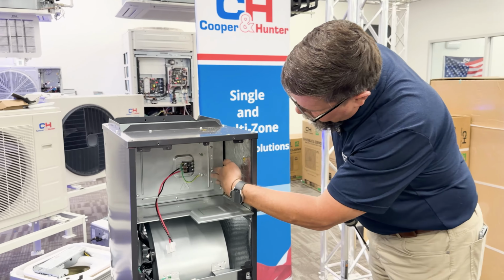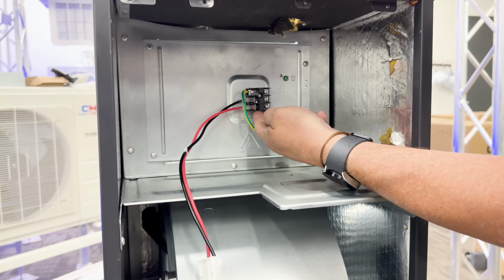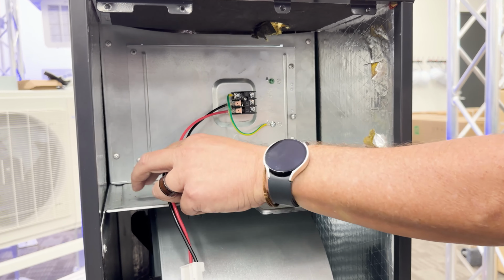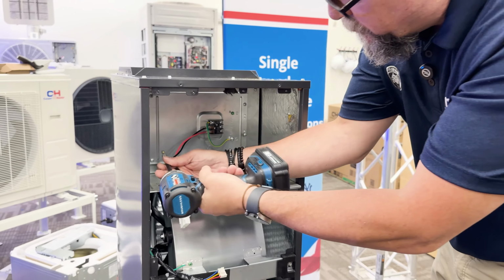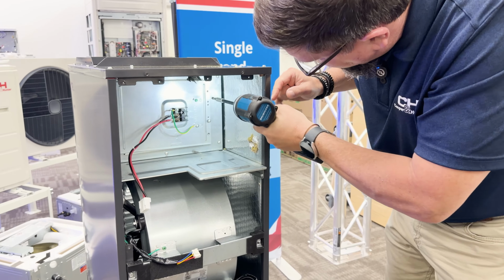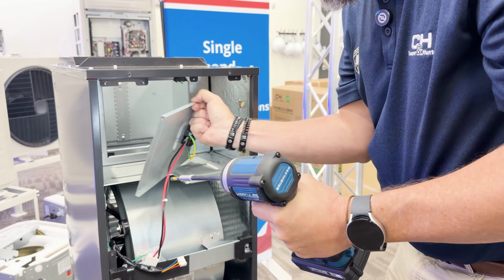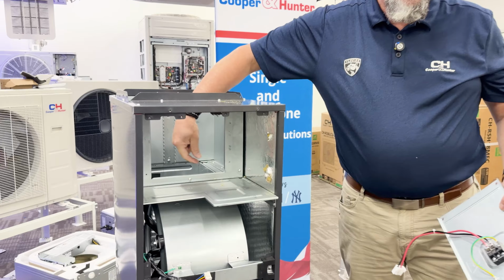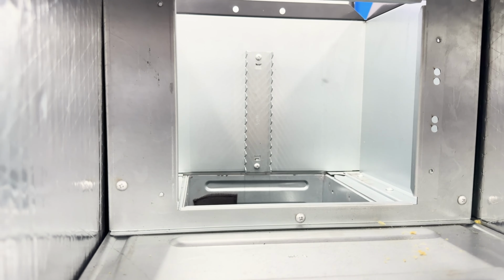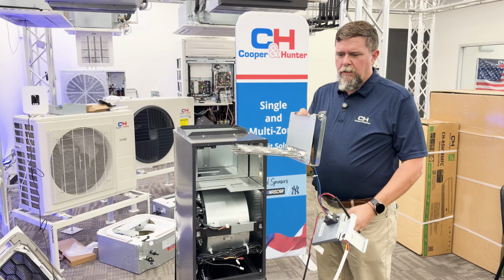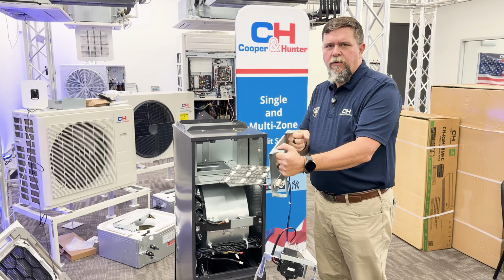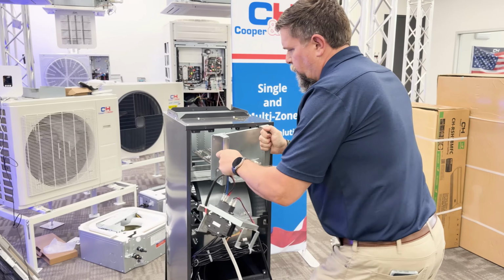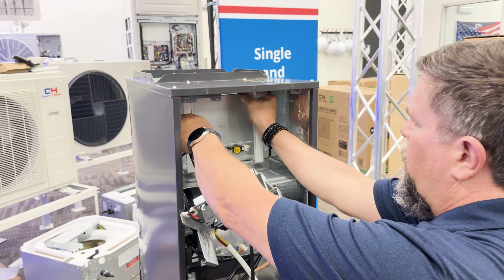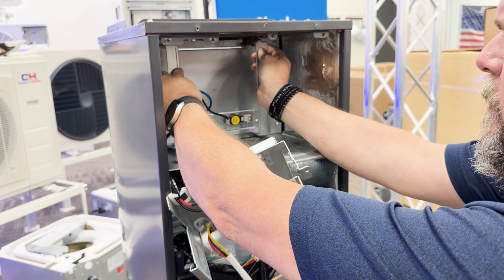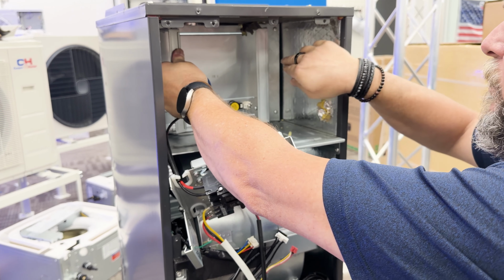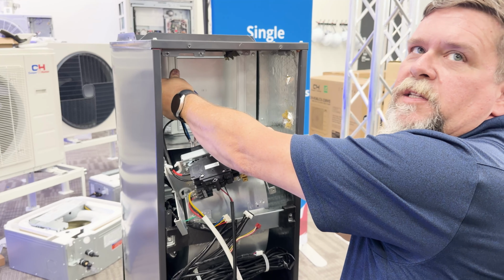Okay. Next step is to remove the plate. You'll see there's 4 screws here. You'll also see the connector for L1, L2. We no longer need that, so we can remove this plate and discard it. And with the plate removed, now you can see there's an opening here where we'll insert our heat kit. The next step is we'll insert the heater itself inside the panel opening. We give you some handles here, and you're going to slowly come in here, and on the back side here, there's a hook for the end to go on there. Line up your screw holes, put in your 4 screws, and the electric heat's mounted.